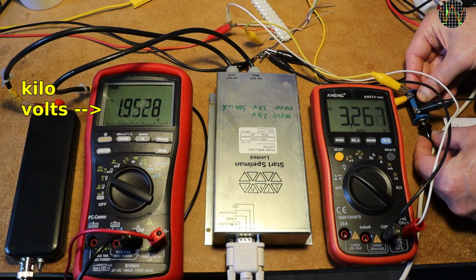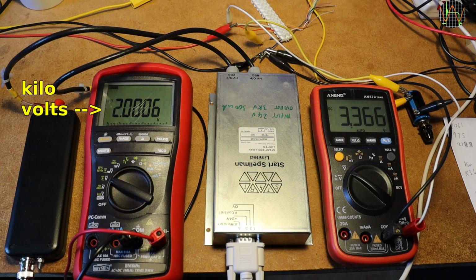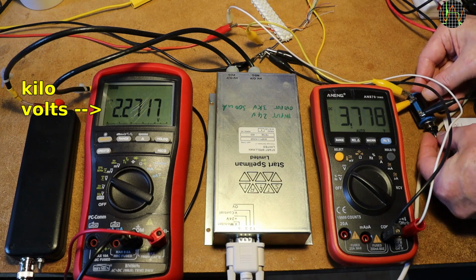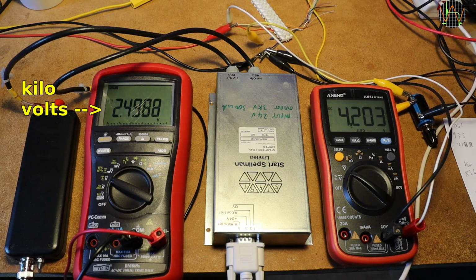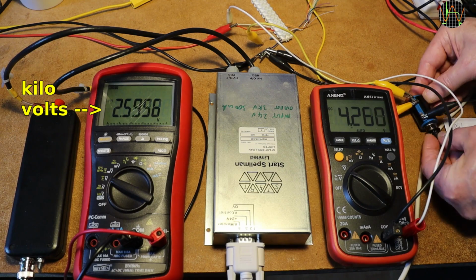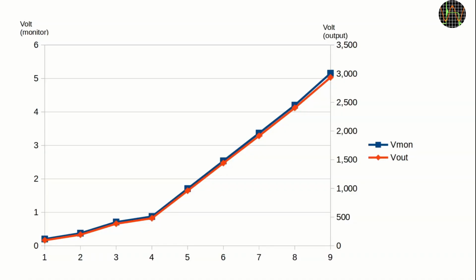As the control voltage increases, the output voltage rises, and so does the monitor voltage. I show this sped up because I was stopping every so often to record the readings of both meters. The result is this graph here. The fact that the traces have this kink is because I was not very careful to always increase the voltage by the same amount. The important fact is that they both are nearly on top of each other. That means the monitor voltage is a true representation of the output voltage.